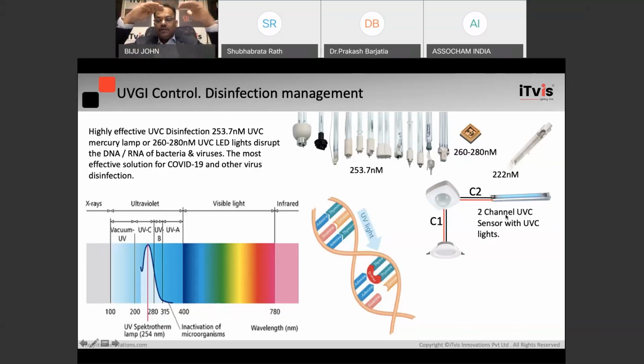The UV light, which is already installed on the ceiling, will be on, and it emits UVC rays at 253.7 nanometer wavelength. And we have design criteria, design parameters. It is assumed, or it is proved, that if you are applying 241 joules per square meter (joule stands for watt second, I'm not going too technical, but excuse me, I need to mention this here), the dosage is in joules per square meter. So if you apply 241 joules per square meter on the virus, its reproducing capability is gone. It's dead.